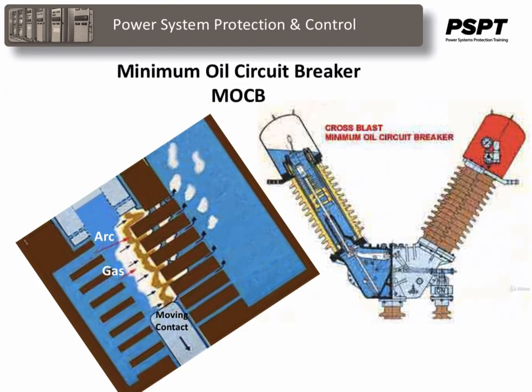In a minimum oil circuit breaker, when opening, the ionized gas around the arc sweeps away through the upper vents and cold oil enters the arcing chamber through the lower vents in an axial direction. As soon as the moving contact tip crosses the lower vent opening, a final arc quenching occurs. The cold oil occupies the gap between the fixed contact and the moving contact, and the minimum oil circuit breaker finally comes into an open position.